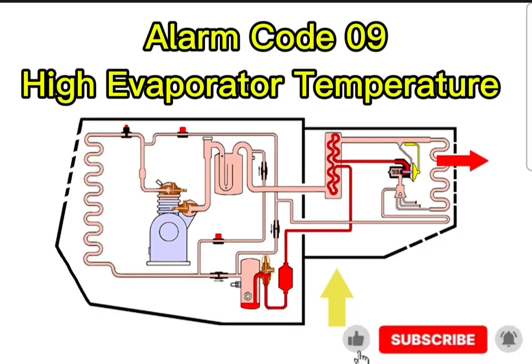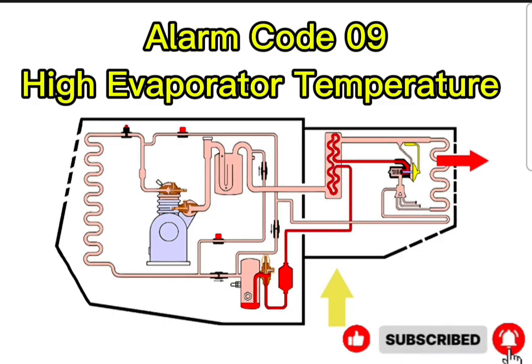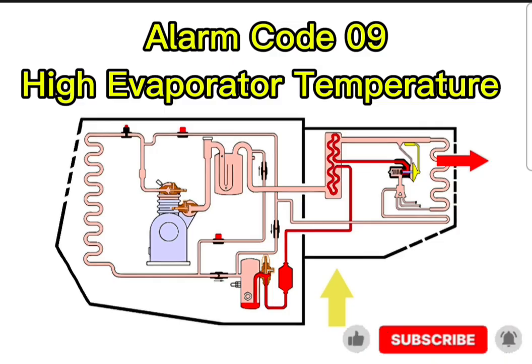This is one of the most dangerous fallback states a system can enter. The manual explains that if both the coil temperature sensor and the discharge temperature sensor fail simultaneously, say a wire gets pinched or shorted out, the microprocessor loses its ability to monitor the internal temperature. It goes completely blind. It can no longer terminate the defrost cycle based on when the ice is actually melted. Instead, it falls back to a crude backup plan. It terminates on time, which is a terrible guess. The manual explicitly warns, if this occurs, the unit may remain in defrost long enough to cause excessive evaporator coil temperature. The machine is suddenly flying blind, and it has to make a highly destructive guess.